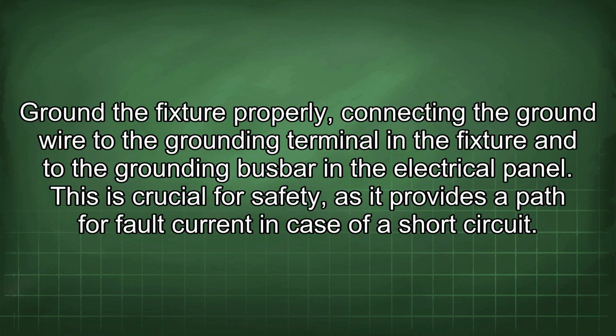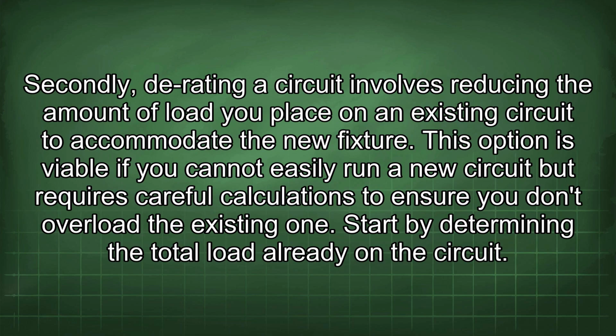Ground the fixture properly, connecting the ground wire to the grounding terminal in the fixture and to the grounding busbar in the electrical panel. This is crucial for safety, as it provides a path for fault current in case of a short circuit. Secondly, derating a circuit involves reducing the amount of load you place on an existing circuit to accommodate the new fixture. This option is viable if you cannot easily run a new circuit but requires careful calculations to ensure you don't overload the existing one.